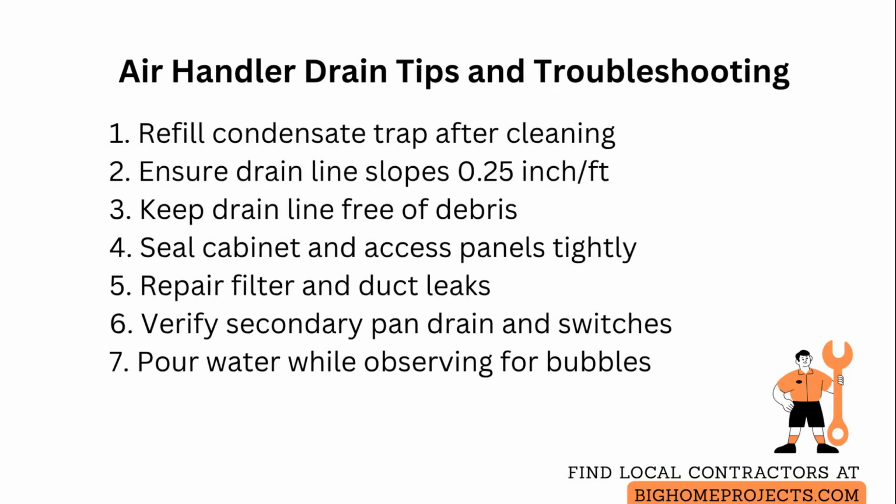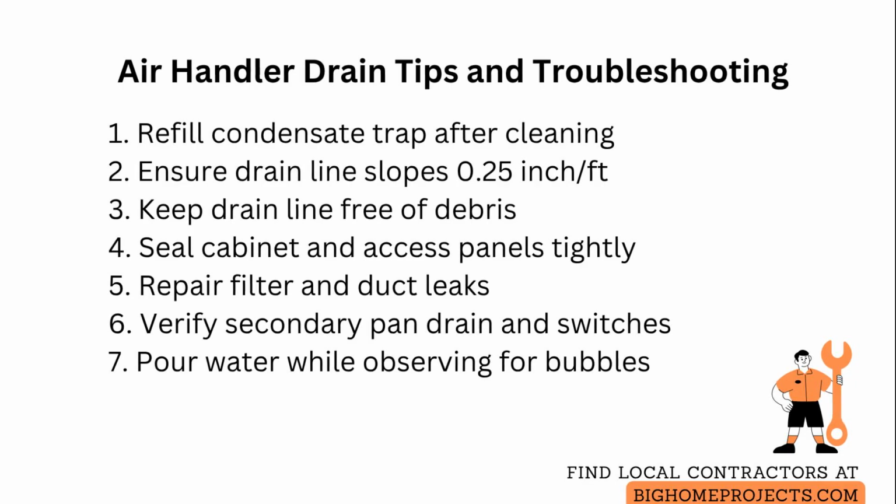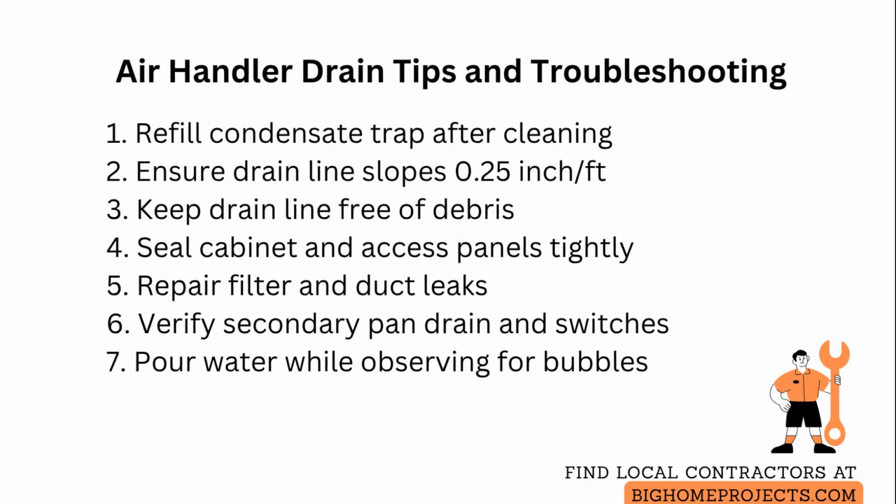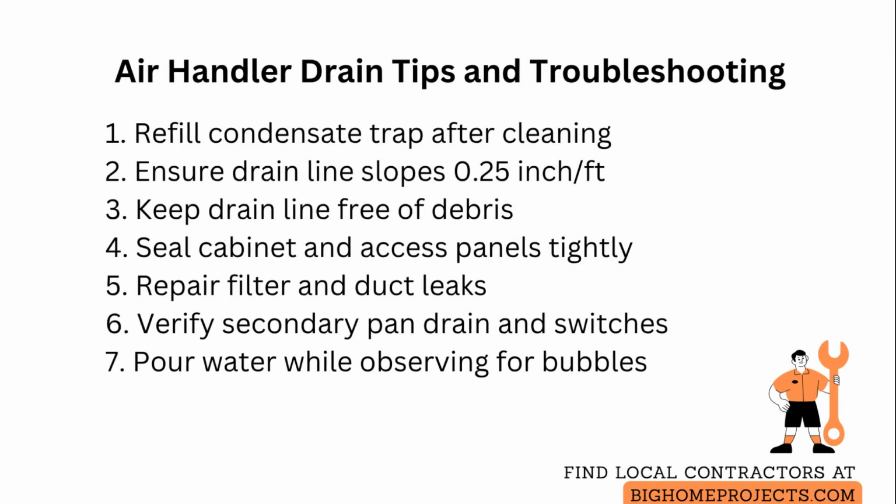To prevent this, always refill the condensate trap with water after any cleaning or service, so the trap seal blocks air movement. Check that the drain line slope is at least 1/4 inch per foot and free of debris. A shallow slope or a partial clog amplifies the effect of any pressure imbalance.